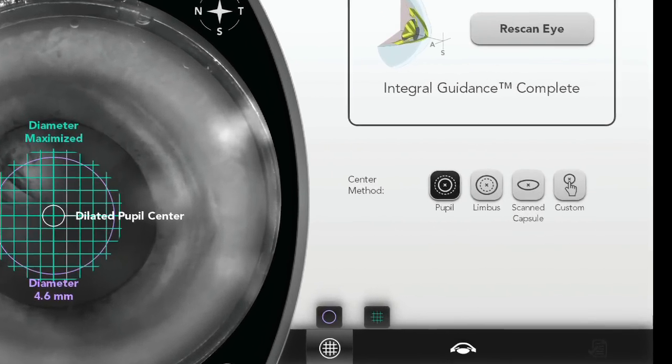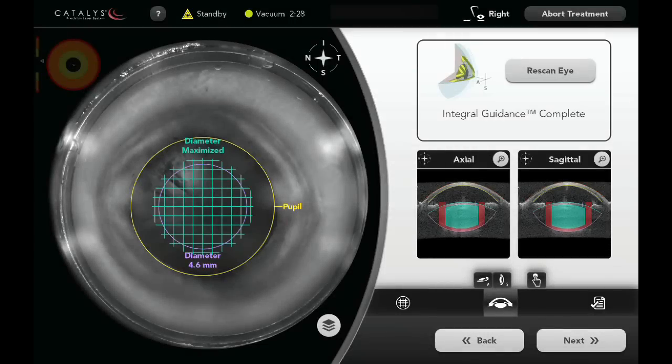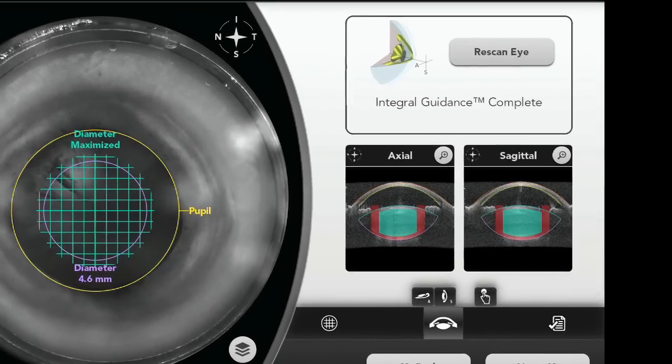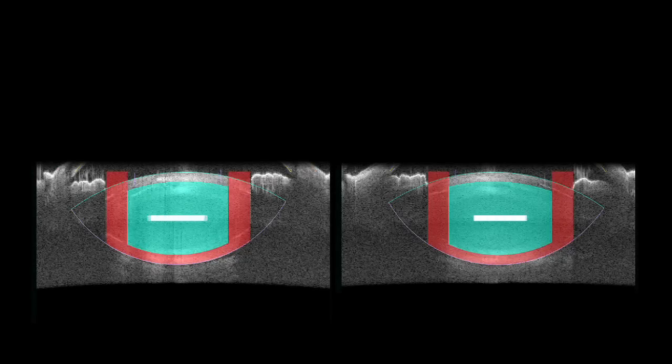With integral guidance, Catalys automatically centers the capsulotomy on the pupil, limbus, or scanned capsule. The system can detect ocular structures and customize the treatment plan even when the eye or the lens is tilted relative to the laser path. Integral guidance also optimizes the lens fragmentation depth by fragmenting deeply while maintaining adequate distance from the posterior capsule.